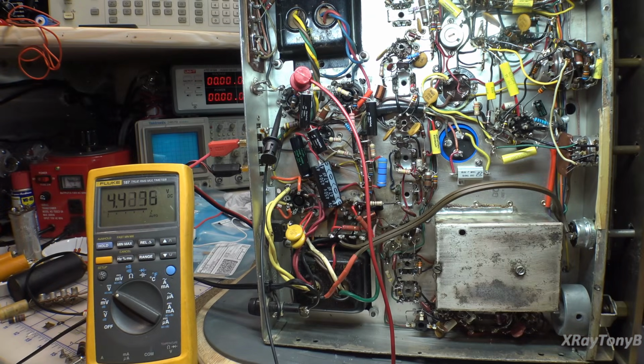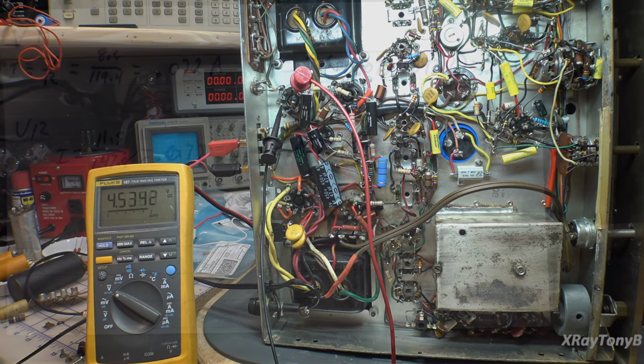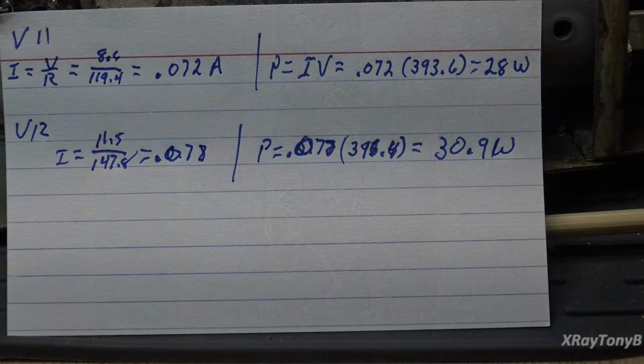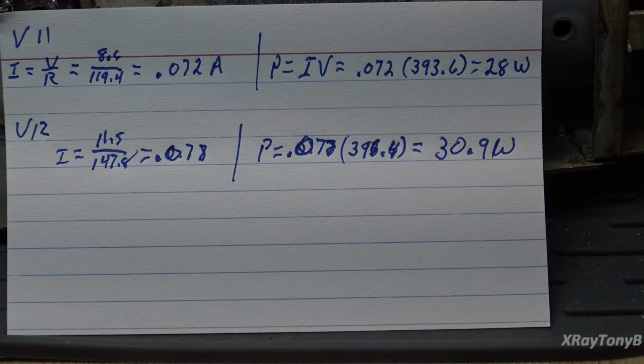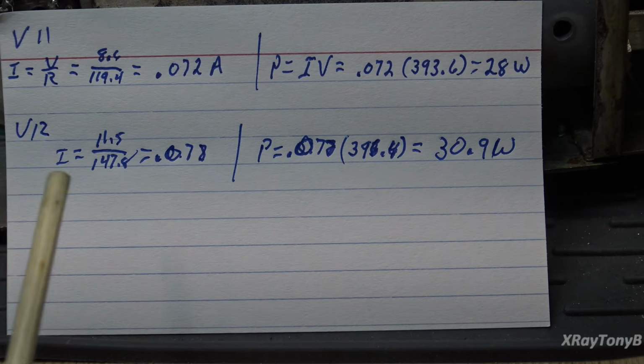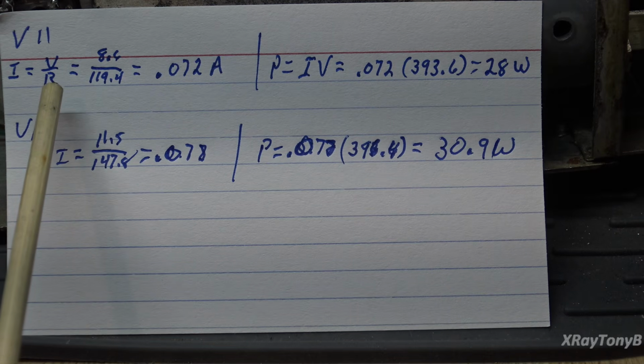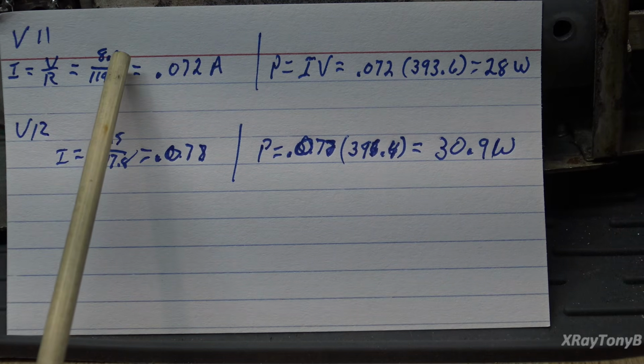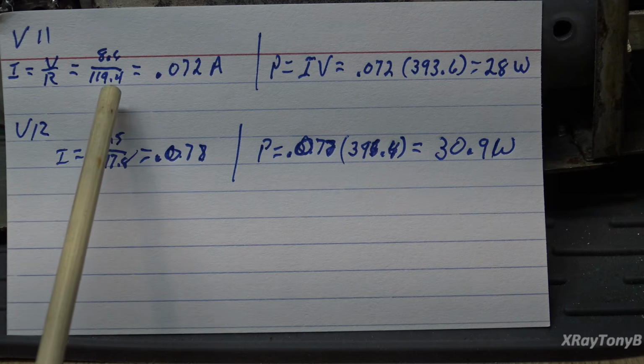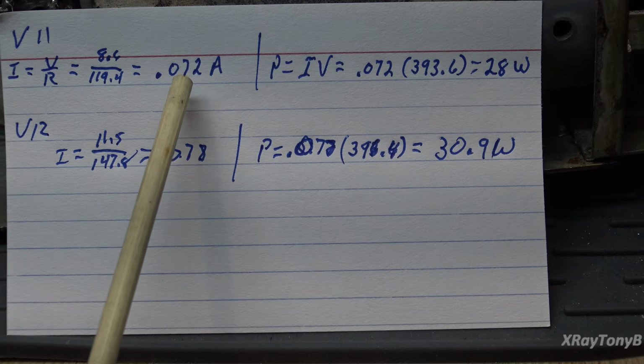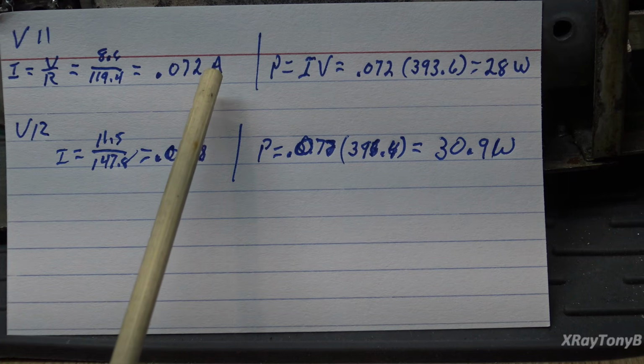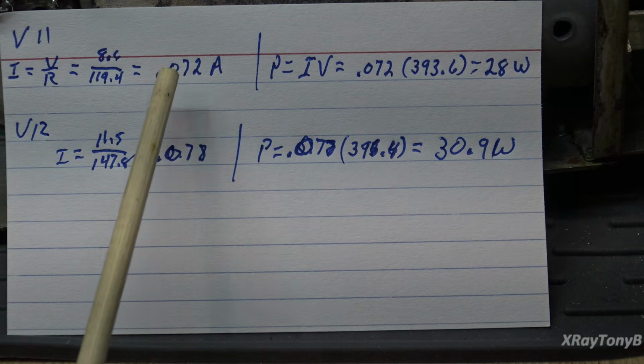Now we have our numbers, let's do a little bit of calculating. Looking at the math, we can see our problem. If current equals voltage divided by resistance, and we take the voltage drop across the winding, which is 8.6 volts on V11, divide it by 119.4 ohms, we get 0.072 amps, or 72 milliamps.